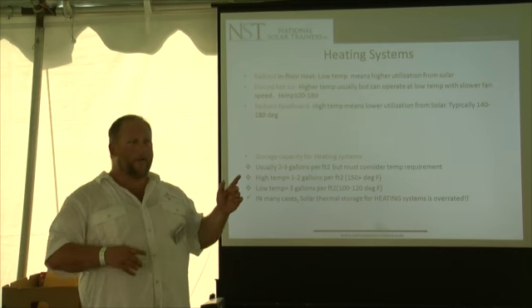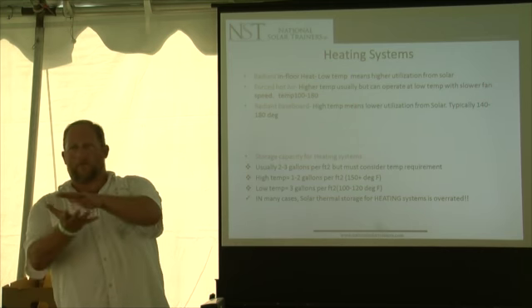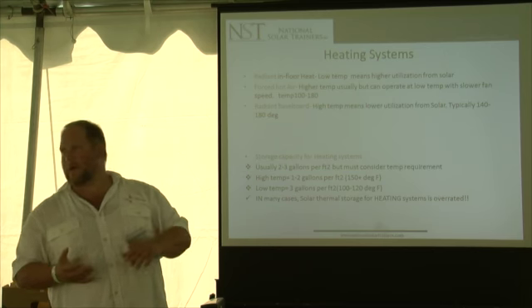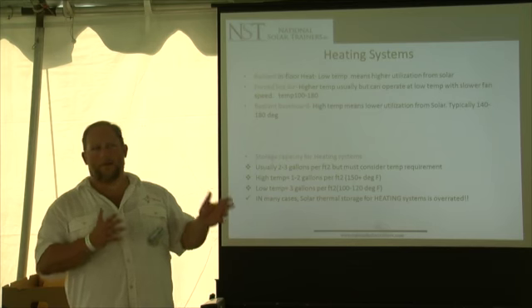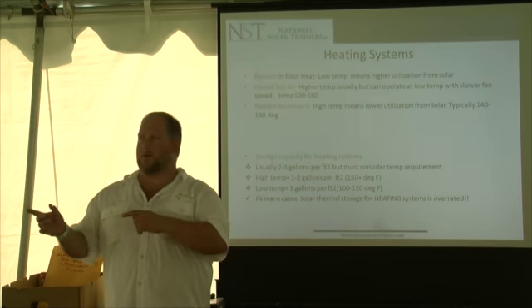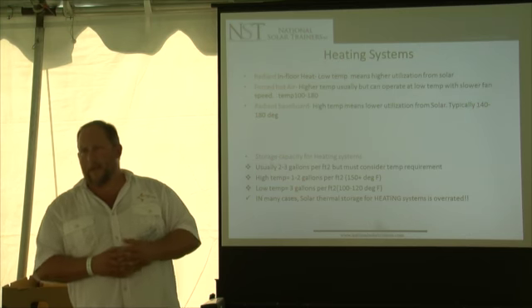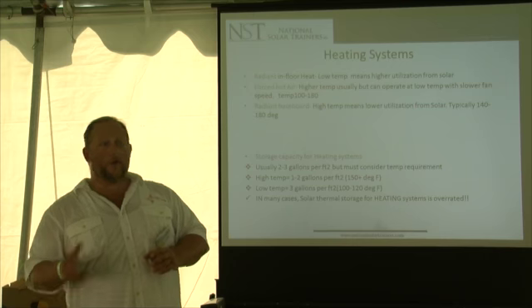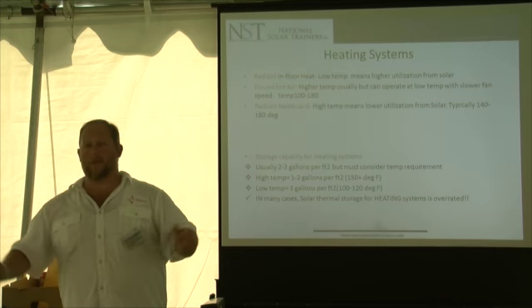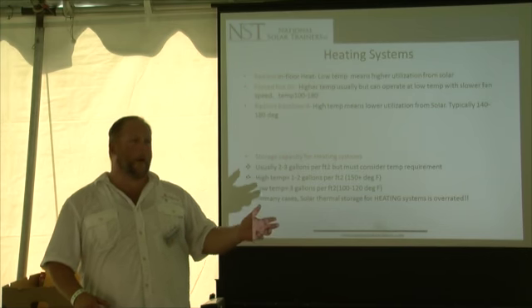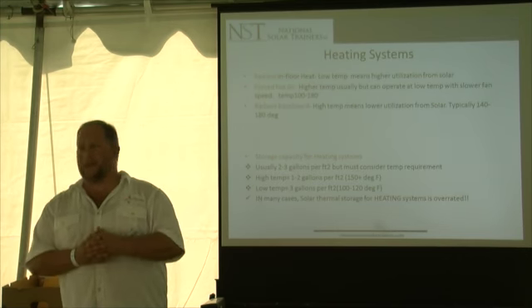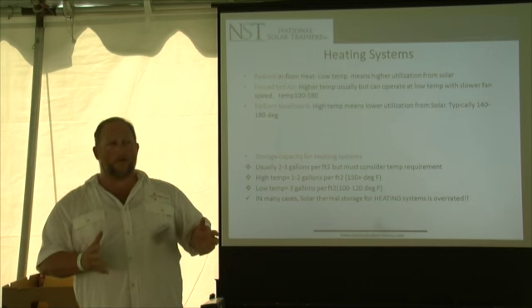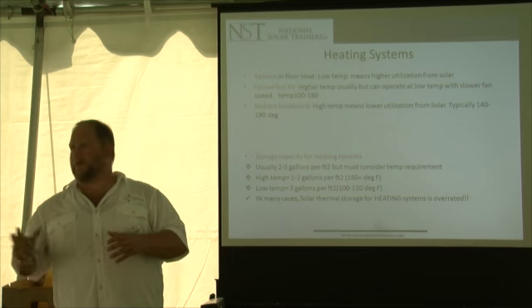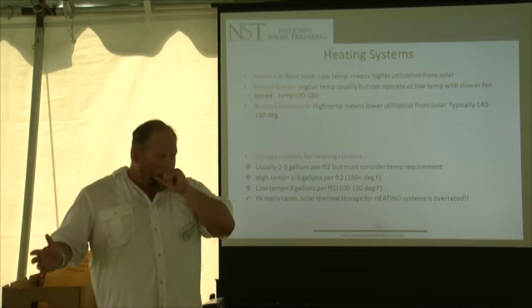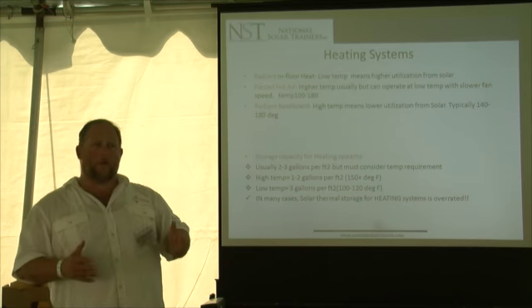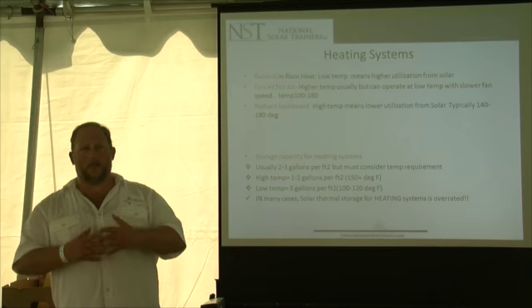Inside that plenum we can put a radiator, similar to your car radiator, and hook that up to the solar tank, so the air moving through the plenum is heated by this hydronic coil. It's easy to dump solar heated water into the furnace through hydronic coils. If you can regulate the fan speed, you can circulate 100-degree air, even 85-degree air, through the house throughout the day, heating the house up to 85 degrees. Forced hot air is one of the least efficient ways to heat a house with traditional fuels, but with solar thermal it becomes really effective because you can circulate air.